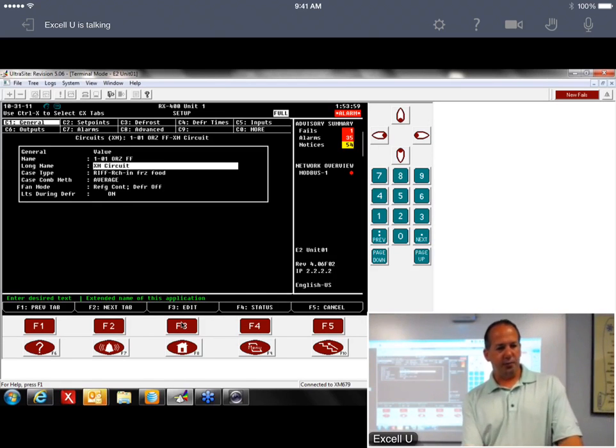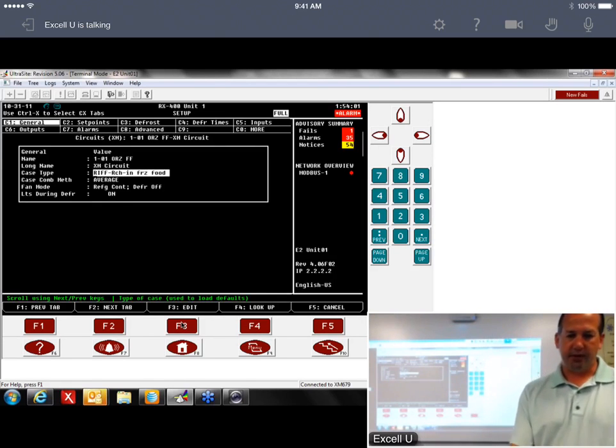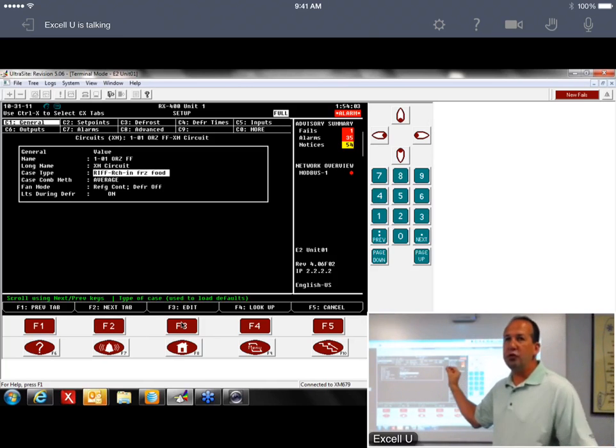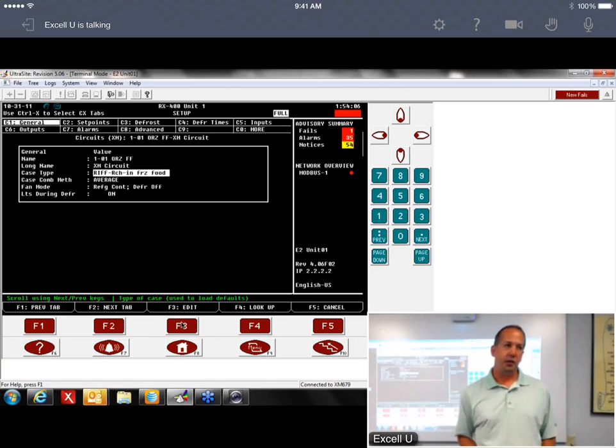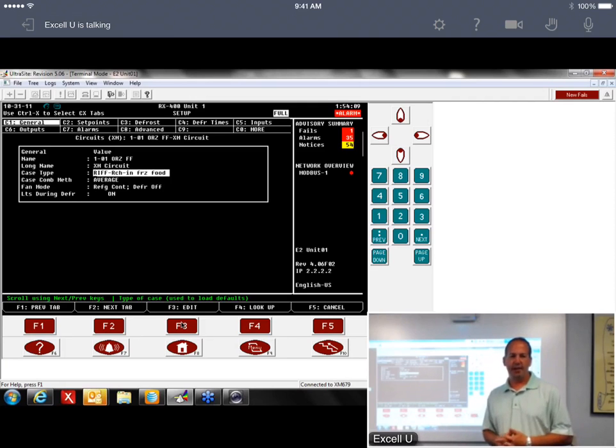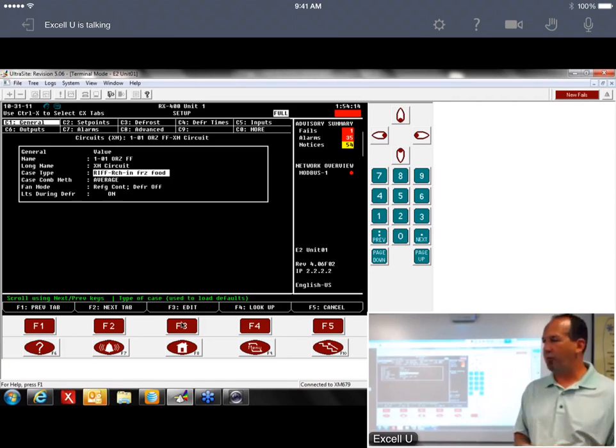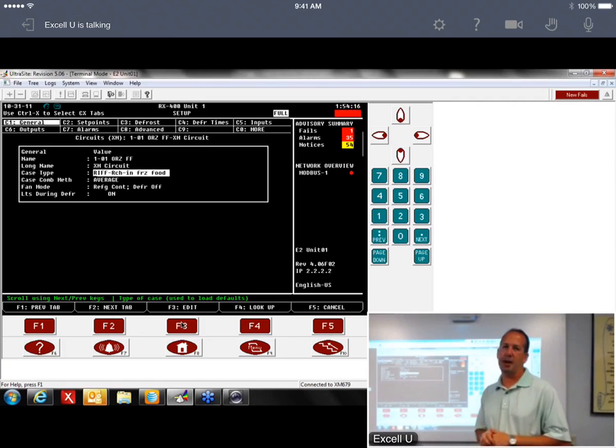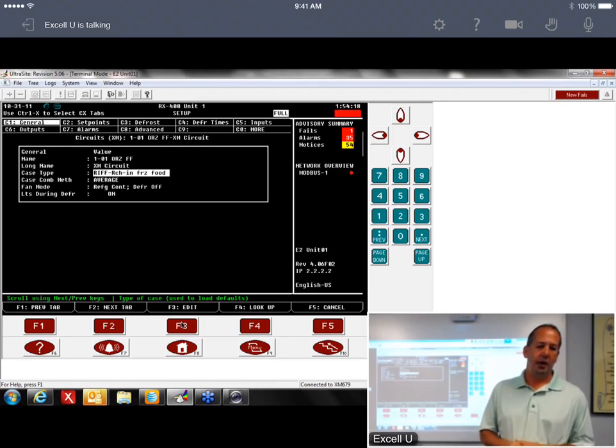Okay, Pete, here's your spot right here, case type on the XM circuit. If you do not put a case type in here, you won't go into defrost. It works that way with all of our circuits. If you don't put anything in that case type, it's not going to work.